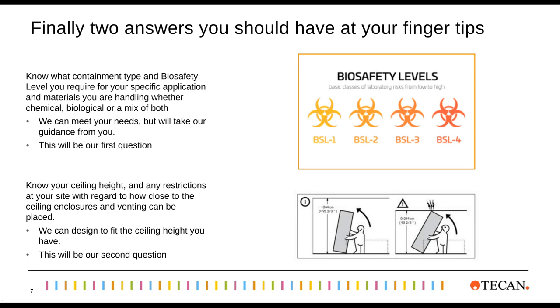And there's nothing worse than forgetting to address this and discovering on delivery day that the ceiling is too low. Make sure you know how tall your ceiling is. More importantly, also make sure you know if there are any height restrictions related to how close enclosures can be to the top of the ceiling, and also any restrictions with regard to how close enclosures can be to venting and any other services within the ceiling. We have a number of design options that can address different ceiling heights, but how tall is your ceiling and what are the restrictions on things like venting will be the second question we ask.